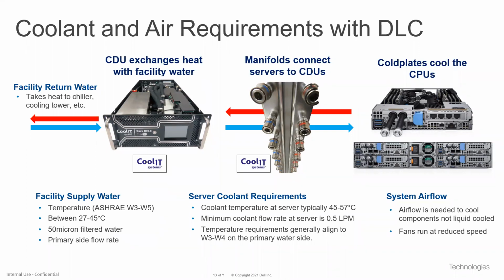The unit to the left is the heat exchanger, what we call the coolant distribution unit. This can come in a small size, such as a rack mount CDU, as we show in this picture, or for larger scale deployments, we can have the in-row CDU, which is typically used to drive 5 racks or more of DLC gear. And that provides some scale economy if you're doing larger scale projects.